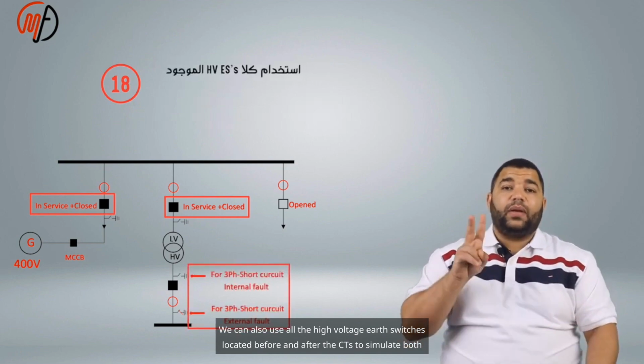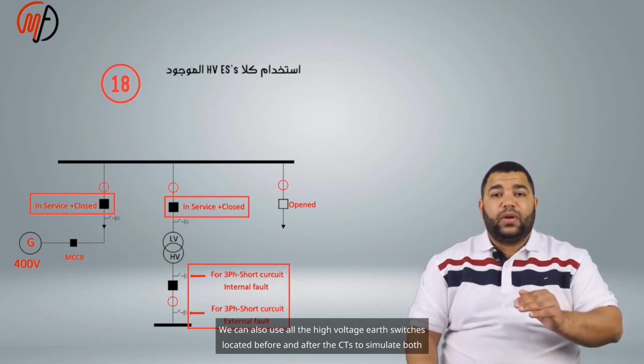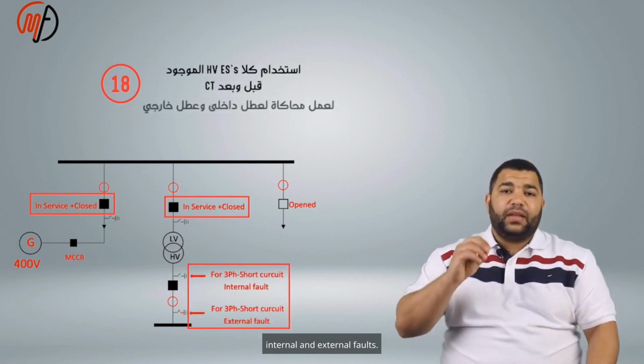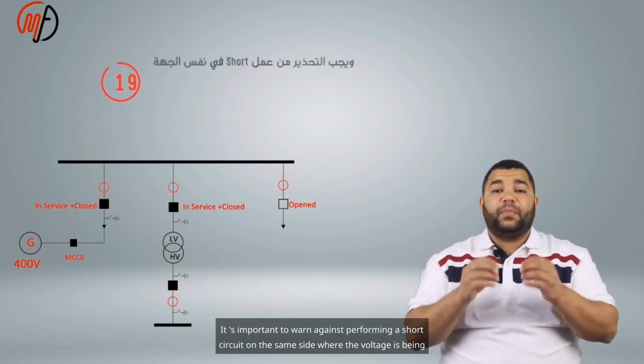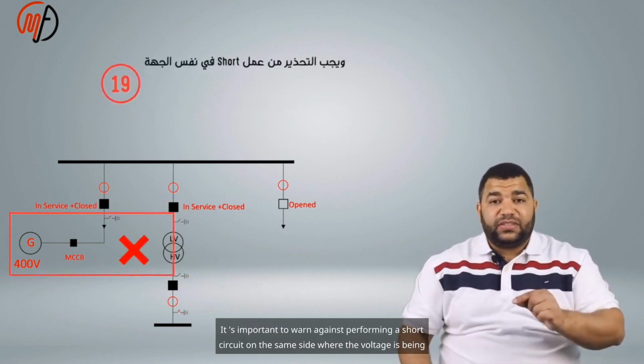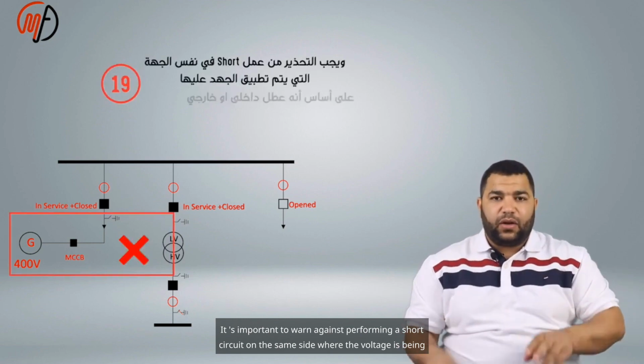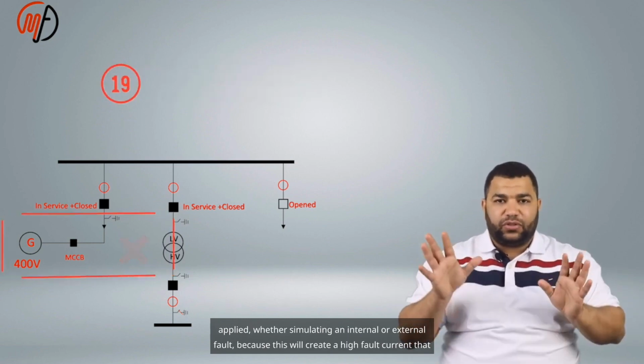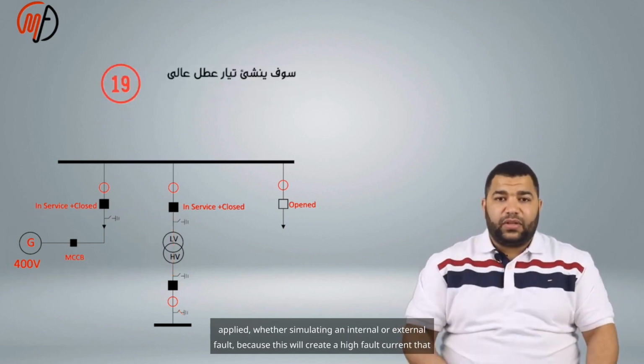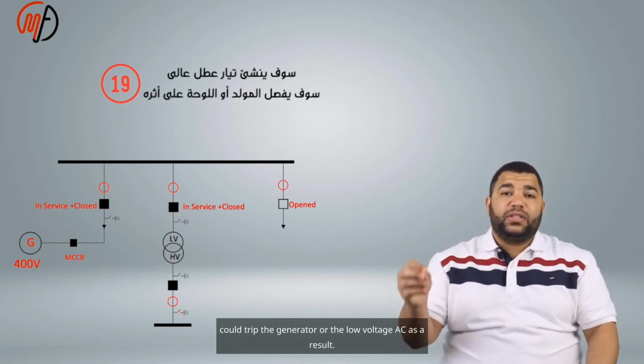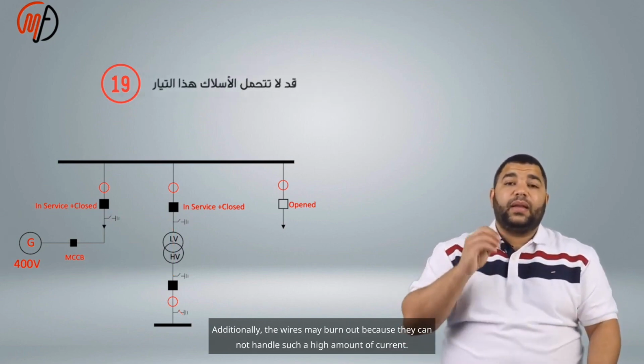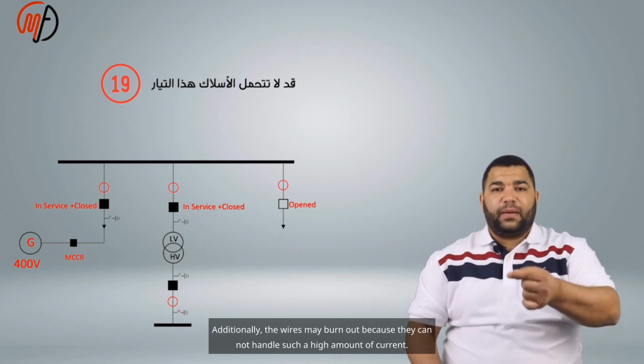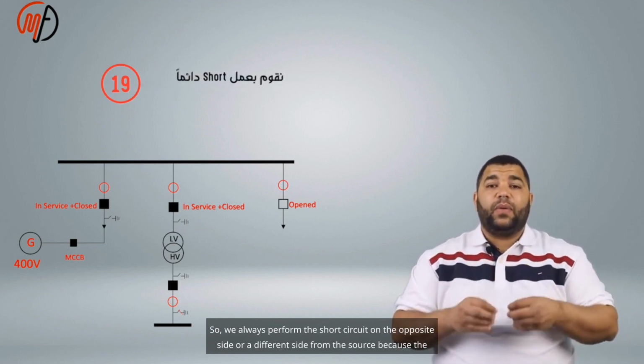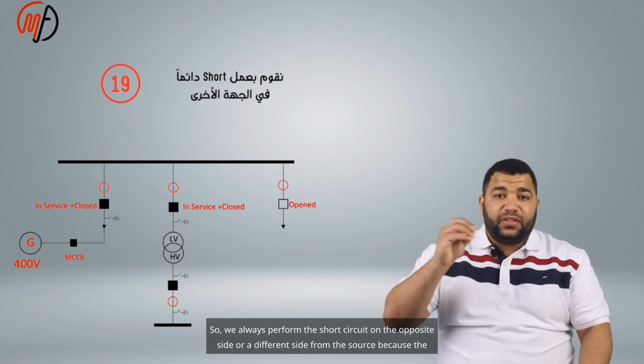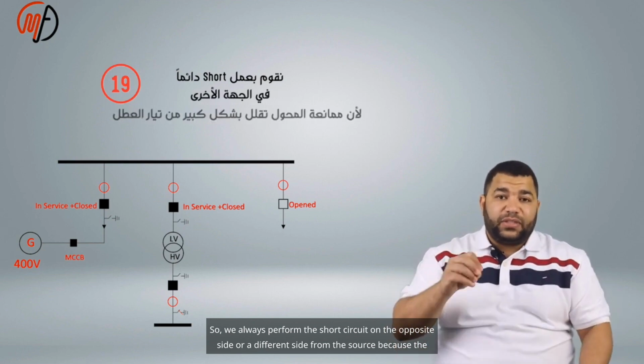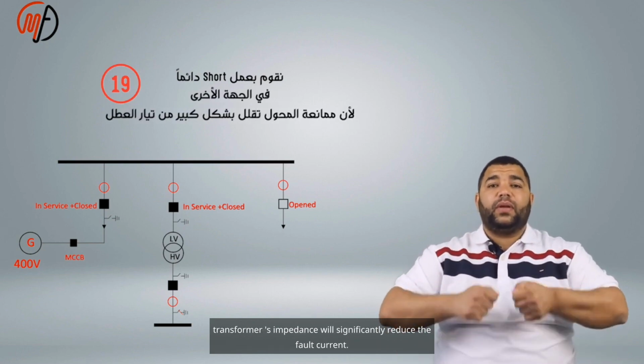We can also use all the high voltage earth switches located before and after the CTs to simulate both internal and external faults. It's important to warn against performing a short circuit on the same side where the voltage is being applied, whether simulating an internal or external fault, because this will create a high fault current that could trip the generator or the low voltage AC as a result. Additionally, the wires may burn out because they cannot handle such a high amount of current. So we always perform the short circuit on the opposite side or a different side from the source because the transformer's impedance will significantly reduce the fault current.